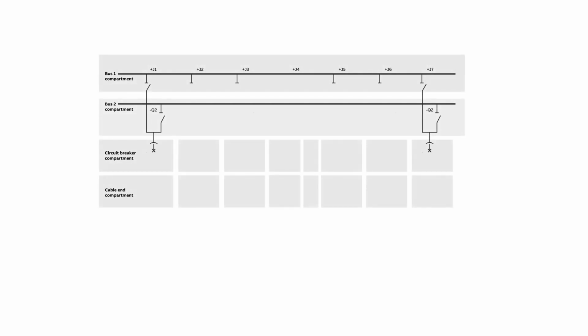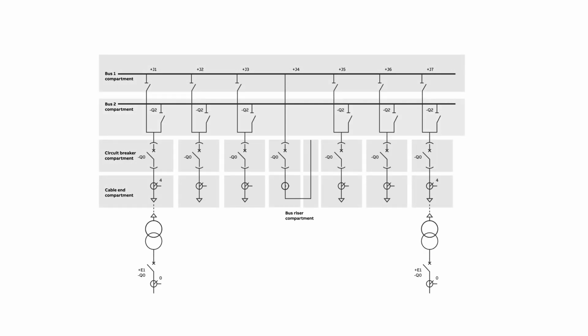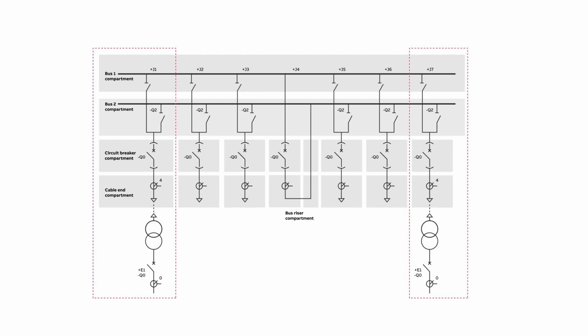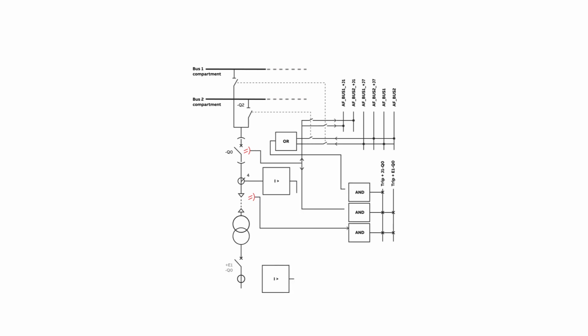He has to consider that the switchgear has 3 different typical bays: incomer, feeder, and bus coupler, and they all have different configurations. In incomer bays, Matthew has to consider that if the arc fault is situated in the circuit breaker or cable end compartment, also the high voltage circuit breaker must be tripped. If the arc fault is in bus 1 or bus 2, the incomer must be tripped only if connected to the faulty bus. To accomplish this, there needs to be 2 arc lens sensors connected to the protection relays. Also, current information from both medium voltage and high voltage measurement points must be used selectively.